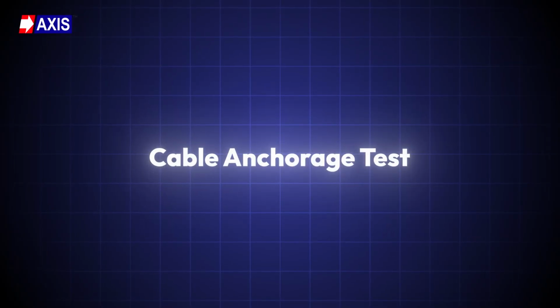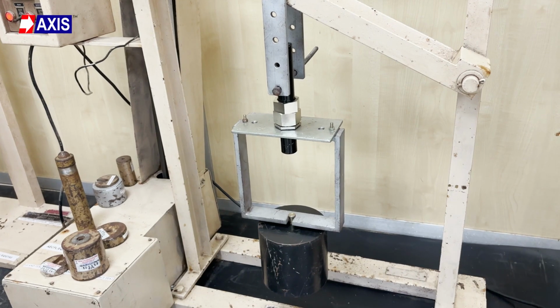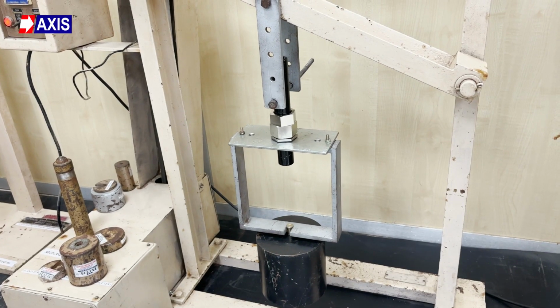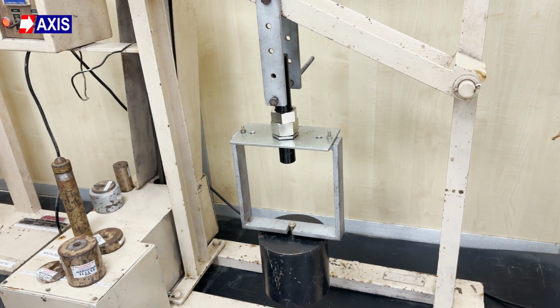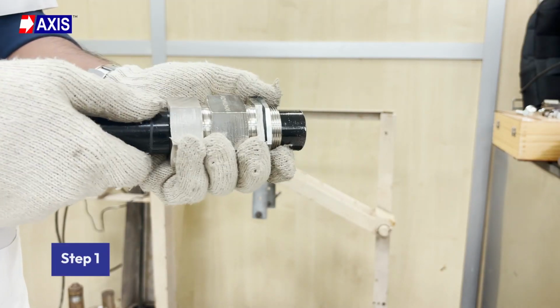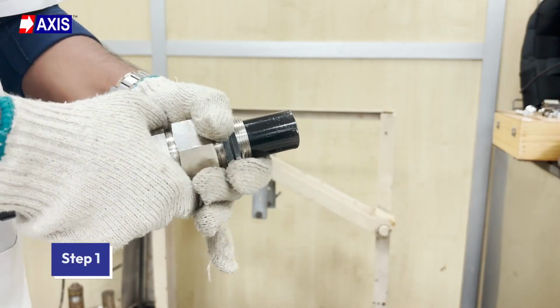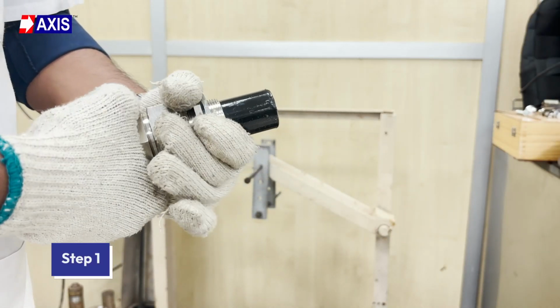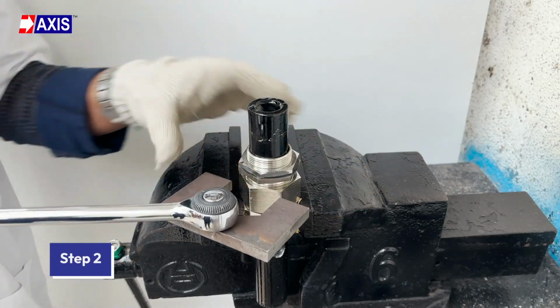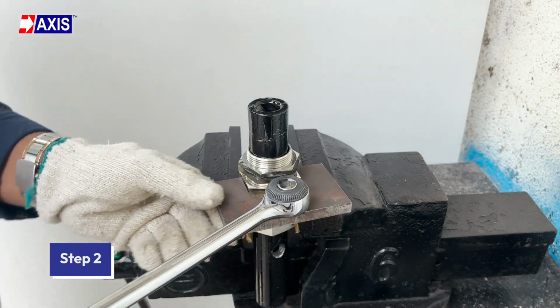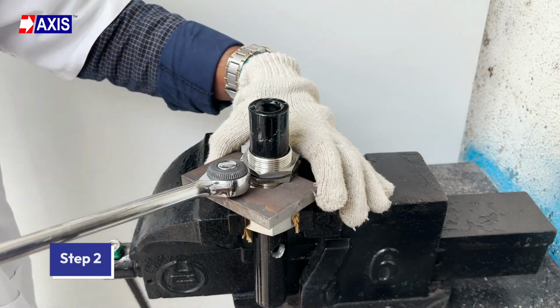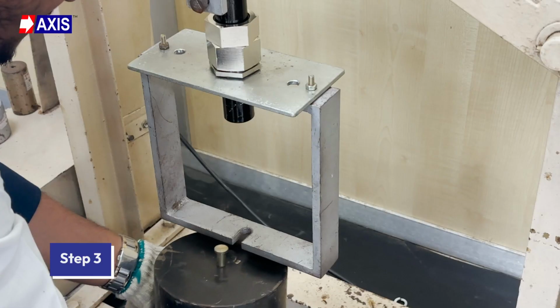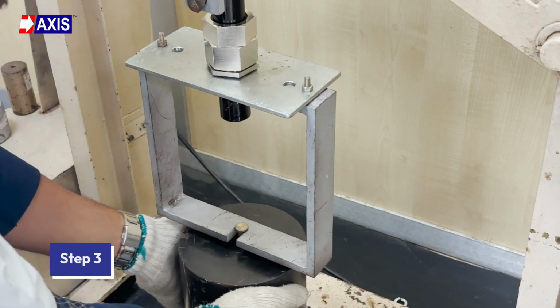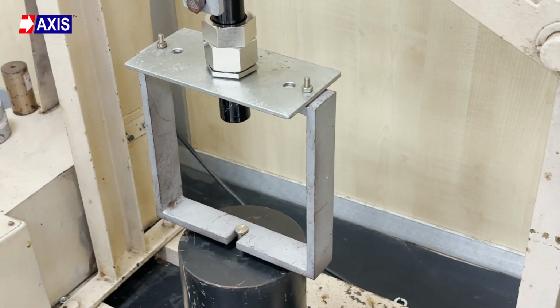Next, cable anchorage test. This test checks how firmly your cable gland holds the cable when it is pulled repeatedly. Step 1. Assemble the gland on a test mandrel that simulates the cable. Step 2. Tighten the gland to the manufacturer's specified torque. Step 3. Apply the tensile load as specified in the standard for the required cable size.